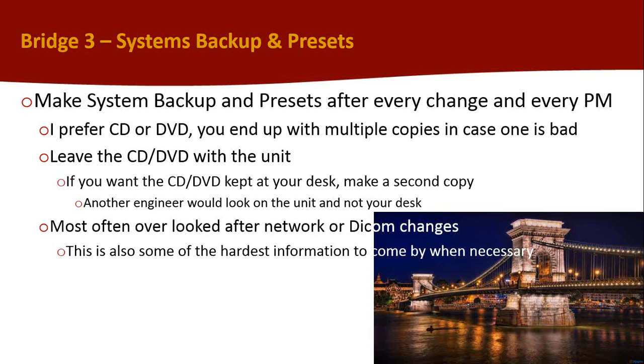So when could you make a system backup or a preset? After every change to the unit and on every preventive maintenance. That's my opinion. That's when I do it. Anytime I come onto a new machine for any reason at all, I make a preset disk. I prefer, generally, on machines that you can do it to, to do it on a CD or DVD. I do not load multiple copies in the same CD or DVD, and the reason is that it's too easy to scratch or lose a single CD. And if all of your copies are on that one CD and you lose that, well, you don't have any extras. Or if that one CD gets scratched and is no longer any good, you don't have extras. But if you have 5 or 6 backup CDs on one unit, at least it'll be close. At least that would be something.